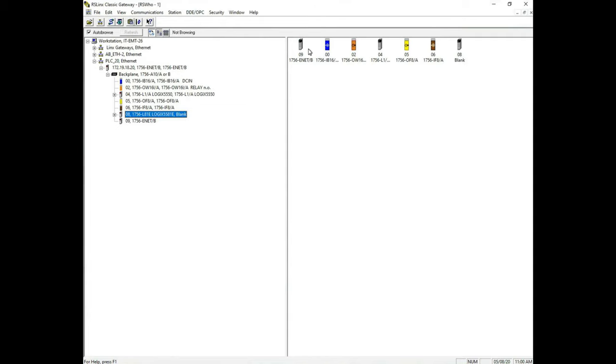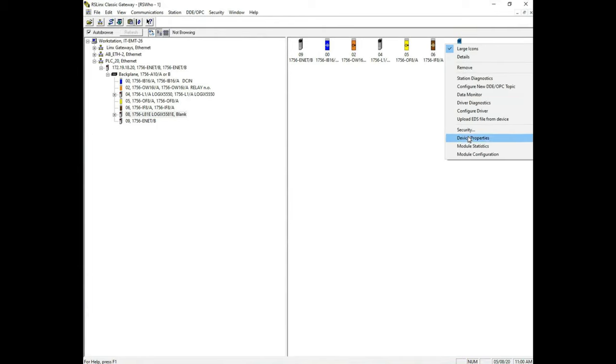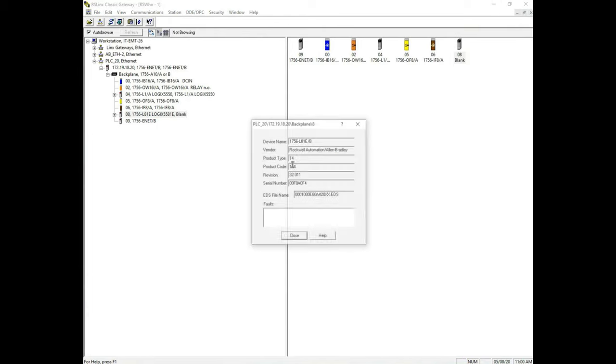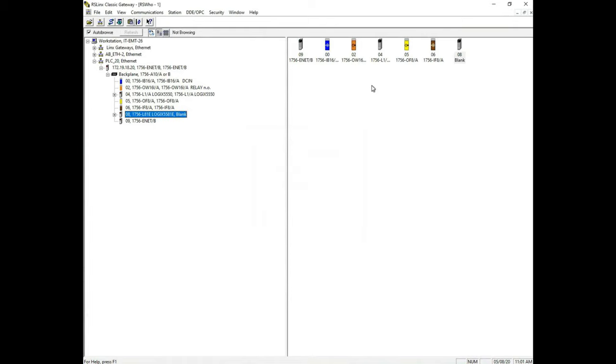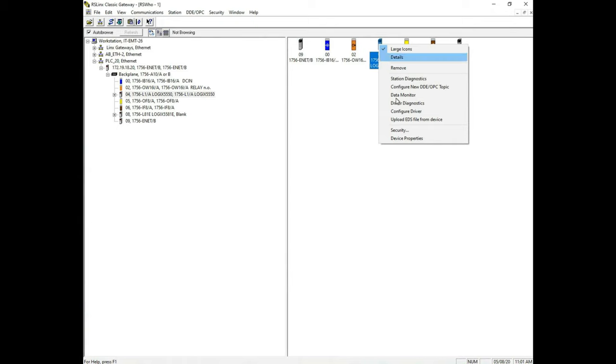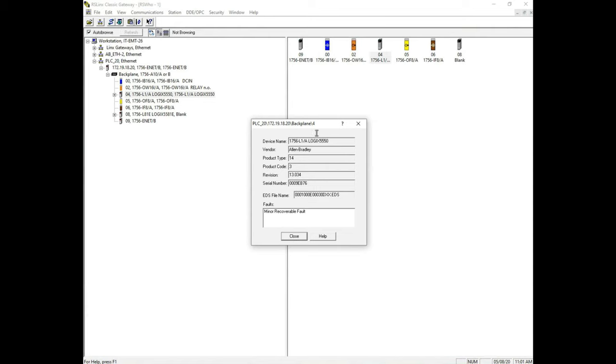I can right click any of these. So let's say that I'm setting my PLC up and I want to know information on my CPU card in slot 8. If I right click this and I go to the device properties, it tells me everything I need to know. This is the newer 1756 L81 CPU card. We know that it's in slot 8 and it tells me here that we have revision 32. Let's compare that to the older card that we have in here, the 5550 card, which is an old card. We'll go to device properties. Now we know that that's in slot 4. That's a Logix 5550 card. And notice the revision here, 13.